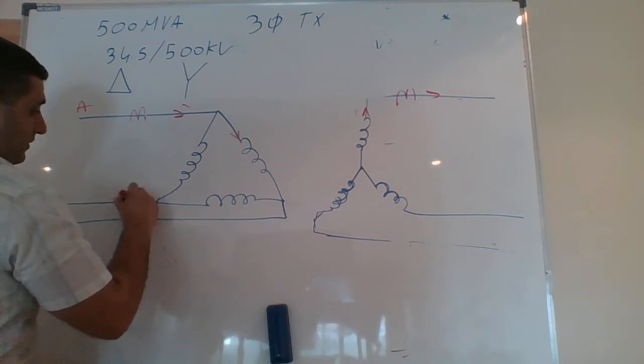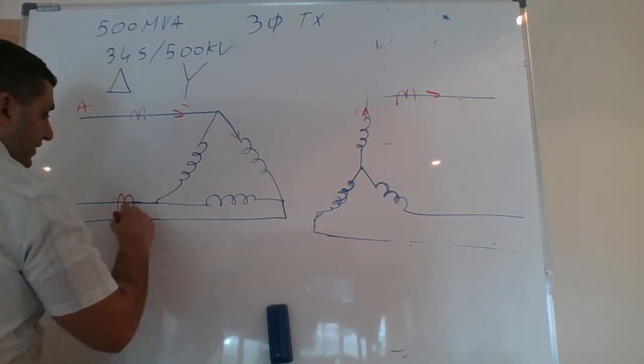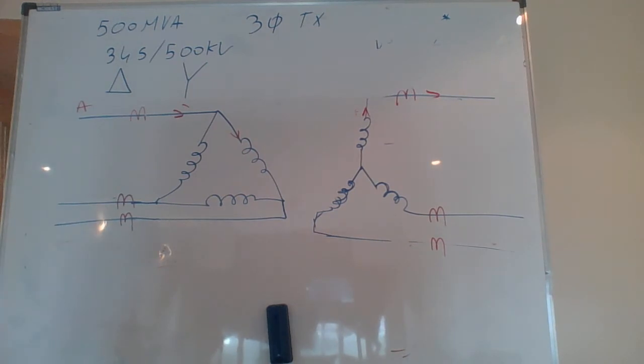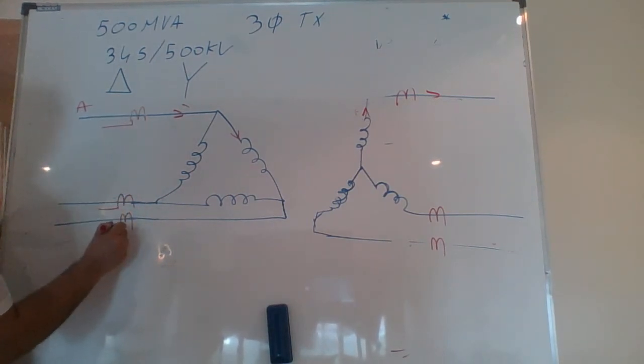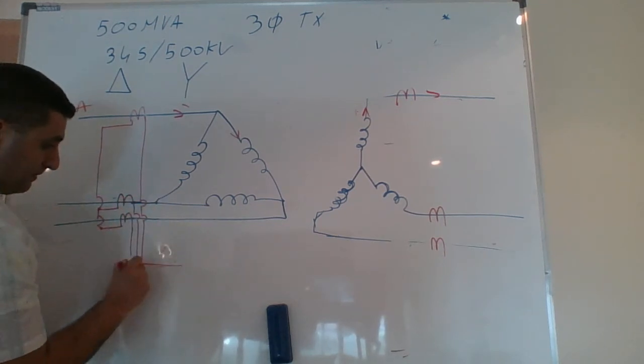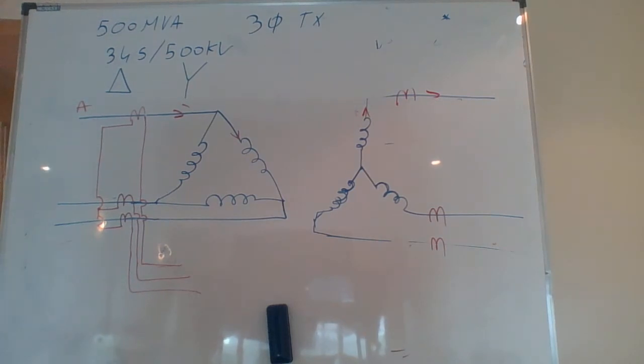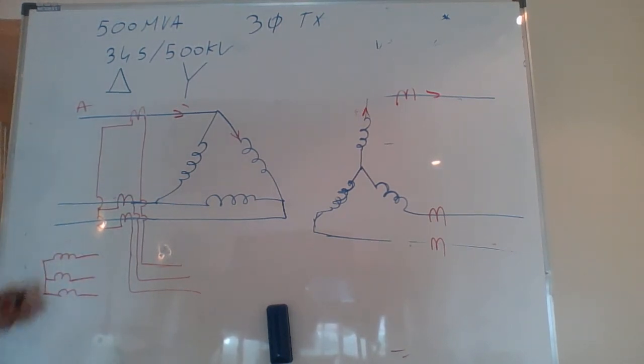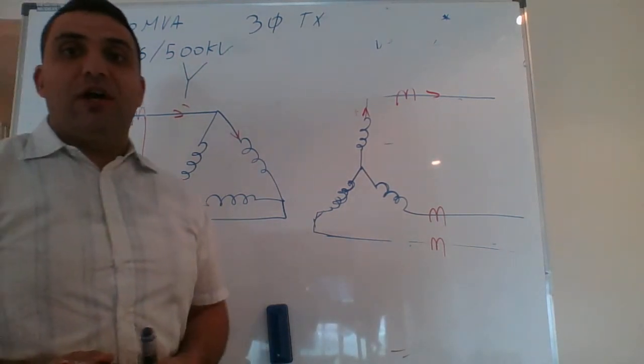Now let me show how to physically connect the CTs. I have three CTs on the primary side connected in Y: I connect one side of them together — this system comes out with three outputs. Each CT has its secondary connected together at one terminal, and the individual outputs come out separately. On the secondary side of the power transformer, the three CTs are connected in delta.